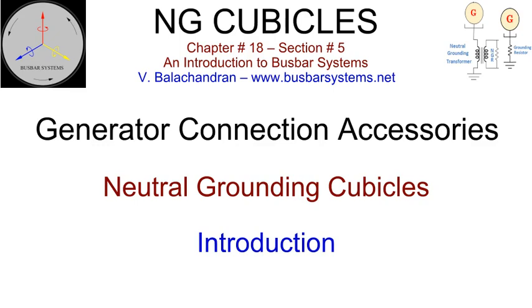Generator connection accessories. Neutral grounding cubicles. Introduction. The major components installed in a neutral grounding cubicle for large generators are a neutral grounding transformer and a neutral grounding resistor. In addition, it may incorporate a single-phase isolator, current transformer for the measurement of neutral current for input to the relay, voltage transformer for the measurement of voltage across the secondary resistance for input to the relay.